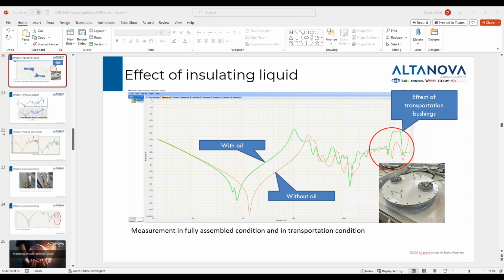Can you perform SFRA on an offload tap changer? Well, not on the tap changer, but on a transformer with an offload tap changer, yes, of course. There's no difference whether it's on-load or offload. The idea is still the same. You test the windings and you measure it as per your routine test plan.